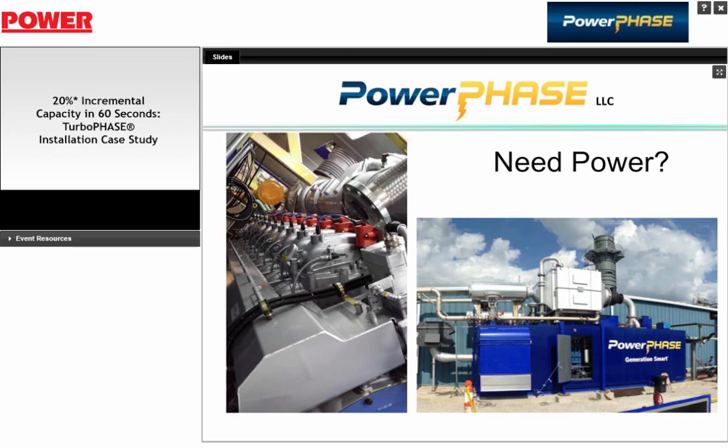All right. Are the Turbophase module units running all the time? In other words, is the 60-second megawatt response based on valve position? No, it's start up the engine and inject the air. All happens in about 60 seconds. So we can go from a dead stop to full air injection in 60 seconds. Okay. If we're running, it's more like 10 seconds.